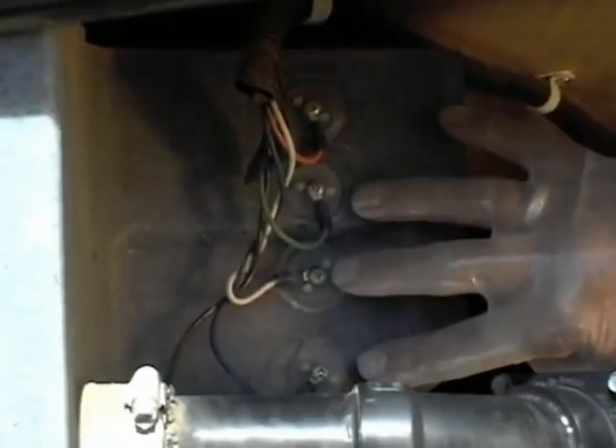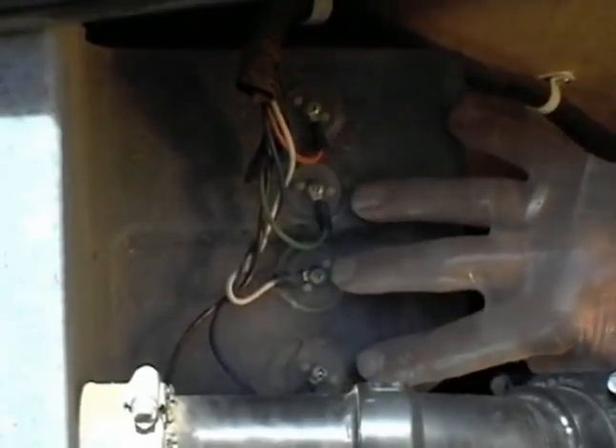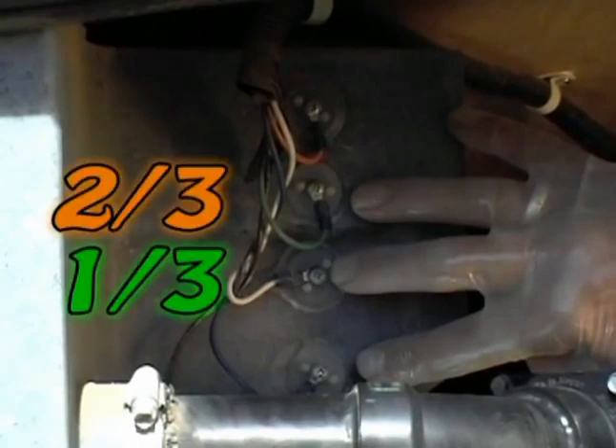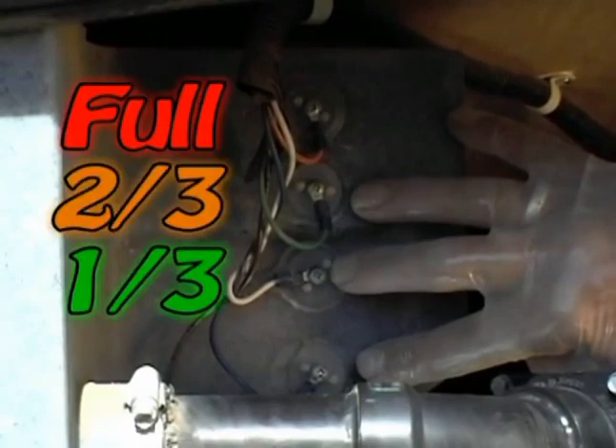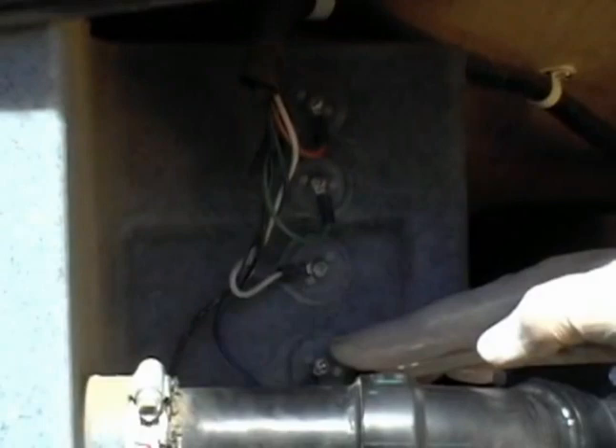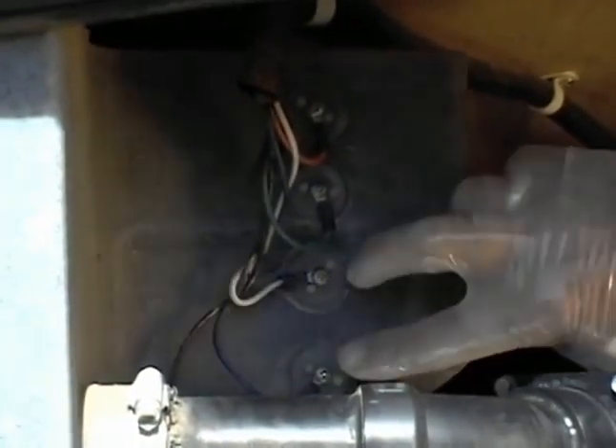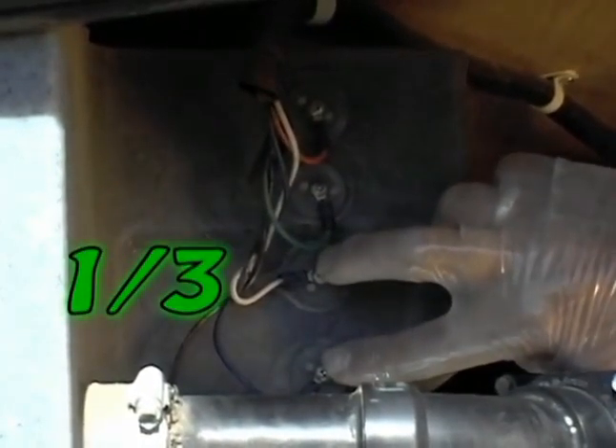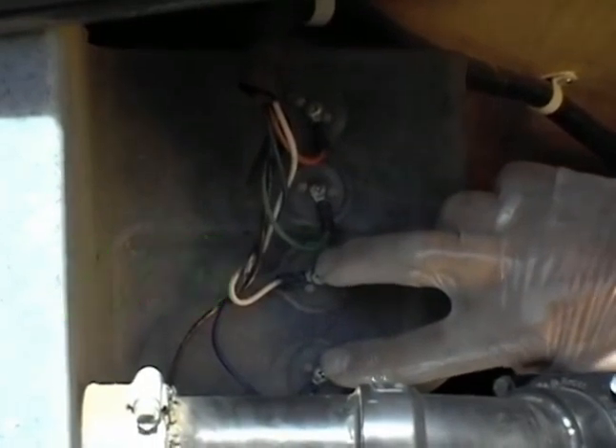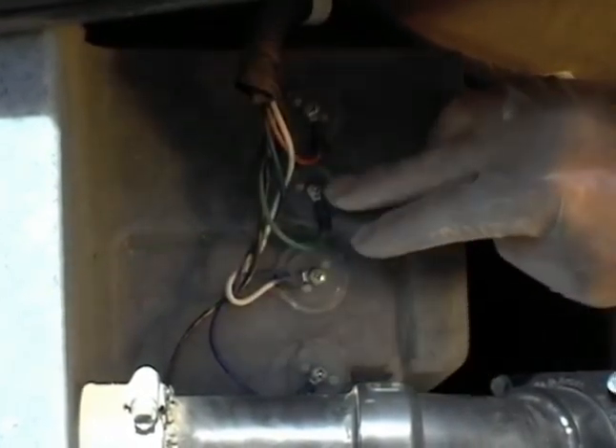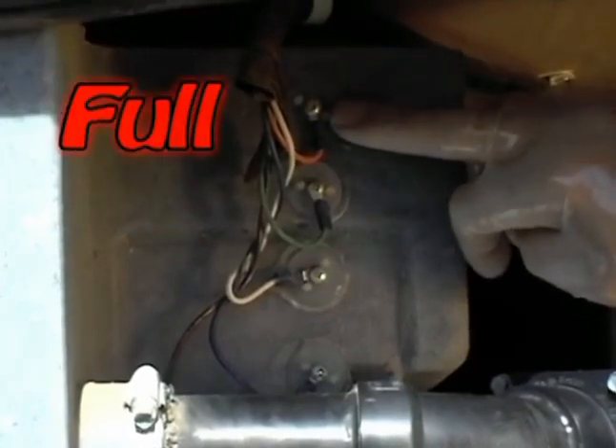These are tank sensors that relay information to the monitor panel. The monitor registers 1/3, 2/3, and full. The power goes to the bottom probe, and when the fluid comes up and touches the second one, it gives a reading of 1/3 full on the panel. When the fluid gets to the third probe, it reads 2/3 full, and of course the final one reads full.